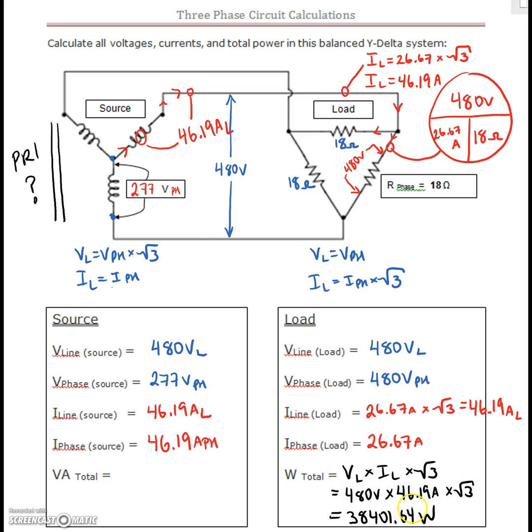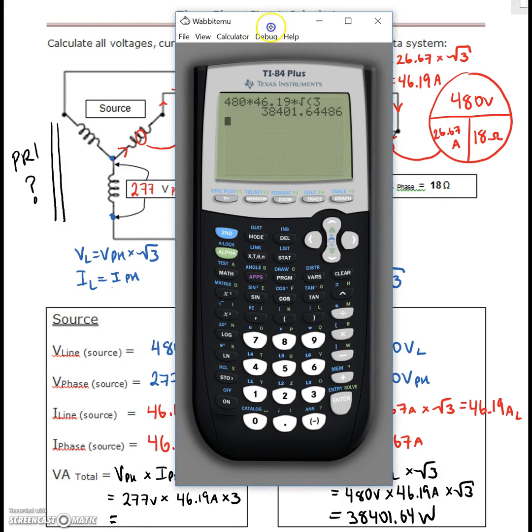And we do watts again because it's just resistive load. We can also double-check that with our phase values. We can do V phase times I phase times 3. Our phase voltage is 277 volts. Our phase current is 46.19 amps. We're going to multiply those single phase values by 3 to get a 3-phase total VA. So what have we got there?